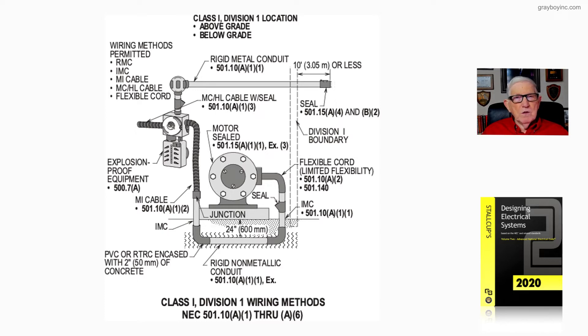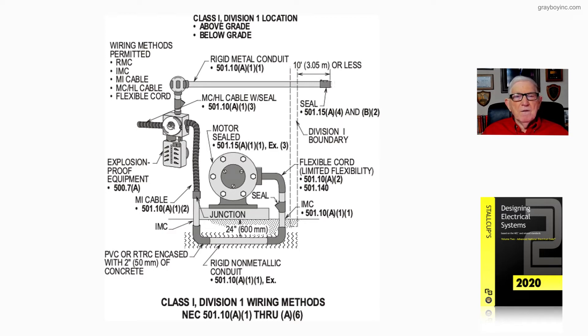Explosion-proof equipment is selected from 500.7A, defined in Article 100 Part 3. You also have flexible wiring methods that you could use in 501.10A2 for flexibility. Basically, you're looking at wiring methods to route from the service equipment or maybe a subpanel to the equipment, and then flexibility connection cables that you might want to use.